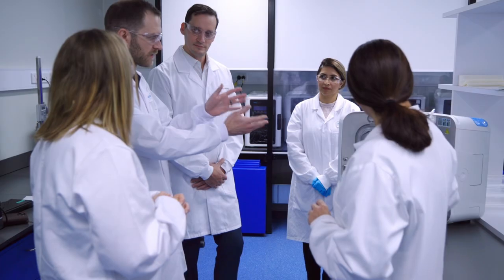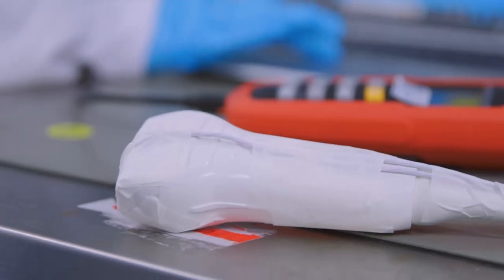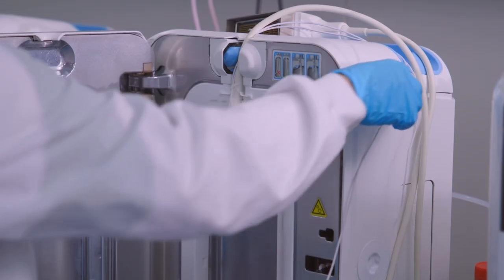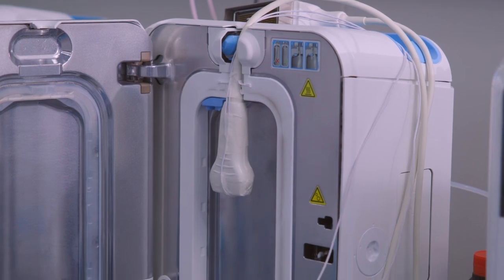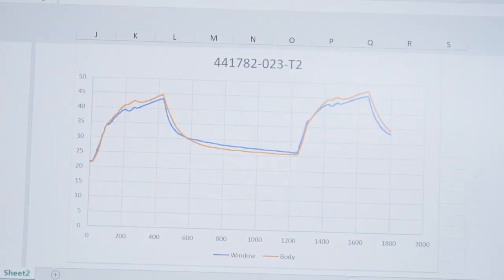Yes. You're not only testing the chamber temperature, which I'm sure the machine does, but you're actually putting temperature loggers and data loggers on the probe itself and measuring that. Yeah, the important areas of the probe, which are the lens of the probe and also the body of the probe. Okay. After that, we check if the probe is compatible with the technology during its lifetime, from day 0 to the number of years that a probe should be in the field.